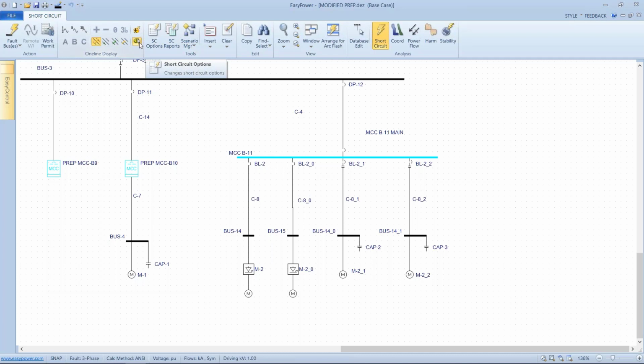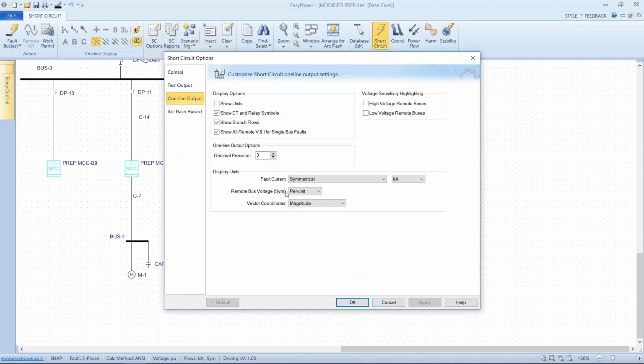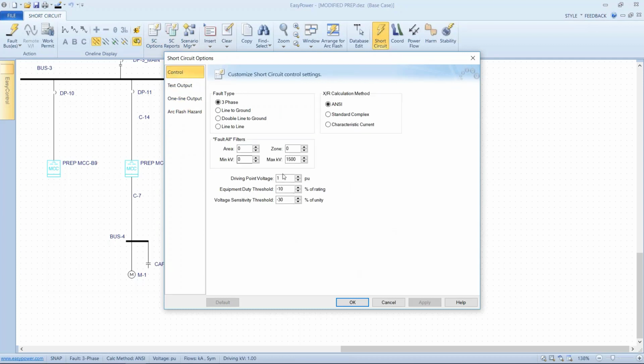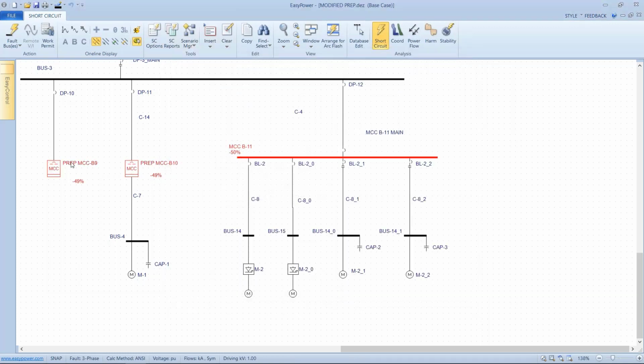Now, if I wanted to see what the real settings were, or the real currents actually end up being, I can either do that on a report, or I can set my threshold at some number quite a bit lower. So I want to look at anything that's within, let's say, 60% of its rating. And that gives me the ability to see if I'm close on anything.